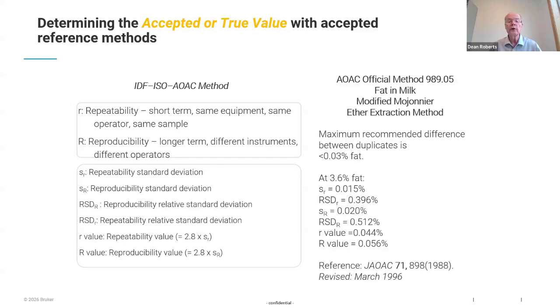And the critical values here are the S sub small r, or the standard deviation of the repeatability, which means you have one operator, one instrument, one set of samples, run multiple times, and what is the standard deviation? And then S sub large r is the reproducibility. So it's the same thing, but it's using different instruments and different operators on the samples. And those are really the limits to what we can expect for the reference values that are used to calibrate our spectrometers. Next slide, Andy.